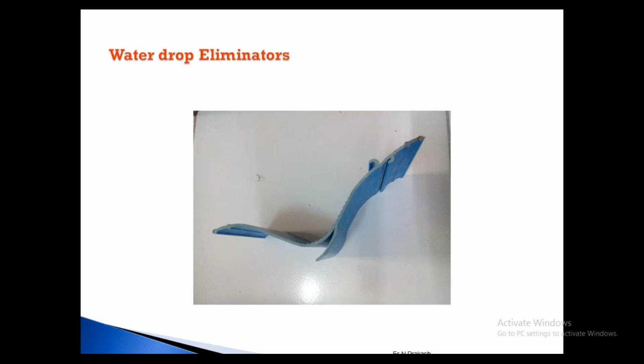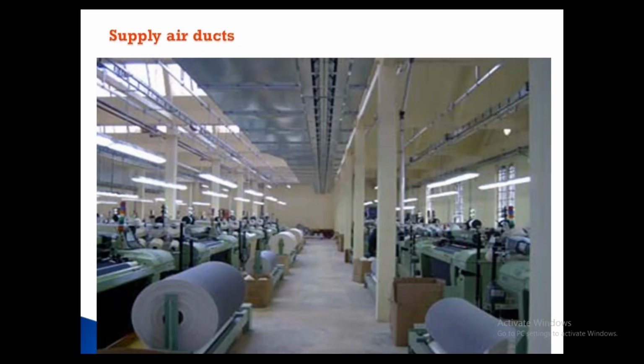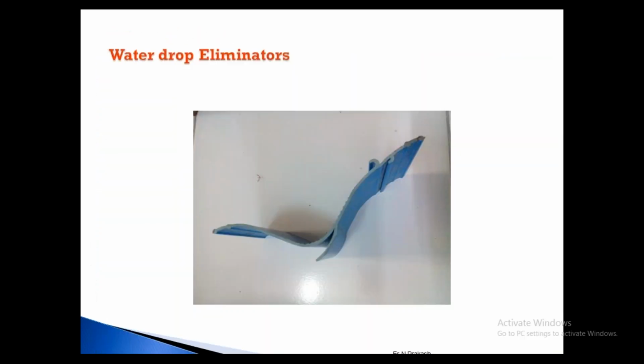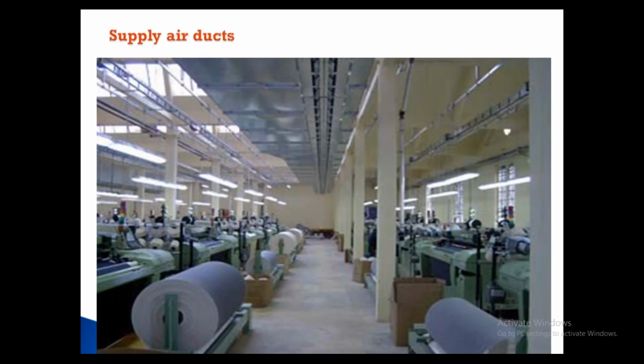So there will be many eliminators. They will be fixed, with either side eliminators at a 20-25 mm gap. Many eliminators will be fixed, the air and water mixture will go inside, and the water will get dropped. So this is the air distribution through the air duct. It is delivered inside your factory.